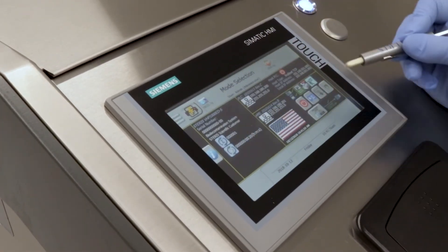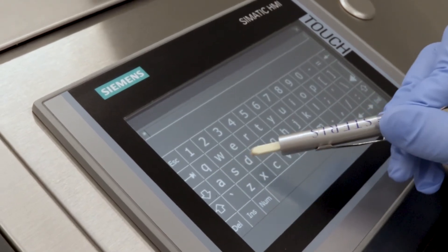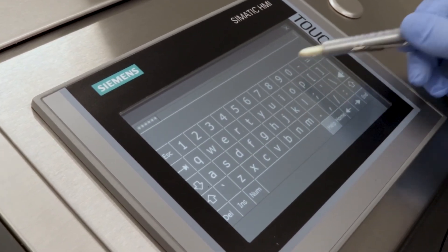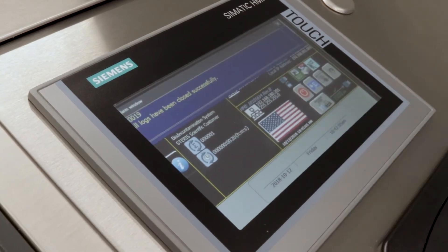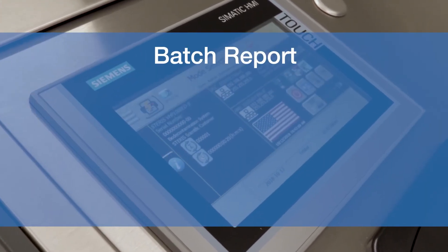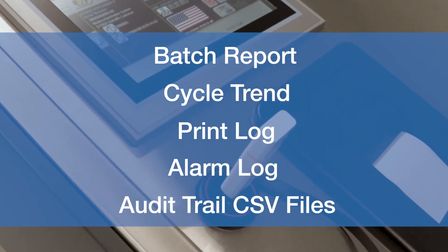Data storage and retention is also a key part of electronic data security. STERIS offers an electronic batch report containing critical records that can be viewed on the HMI and/or exported using the audit viewer feature. Along with a batch report, cycle trend, print log, alarm log, and audit trail CSV files can be copied to a USB drive for storage and printing.